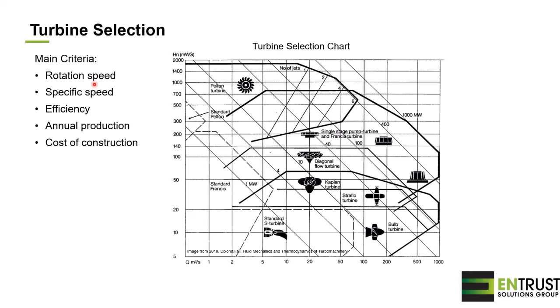It's important to note that a Pelton turbine can be put at ground level, but to be efficient, a Francis or even a Kaplan needs to be put underground as much as possible to extract more power and prevent cavitation. We'll go into that soon. So that will drive the cost of construction if we have to do excavation.